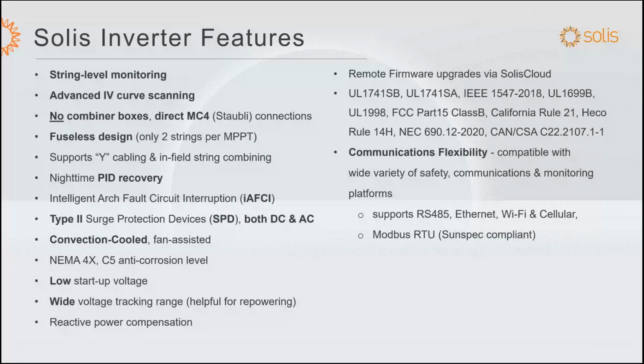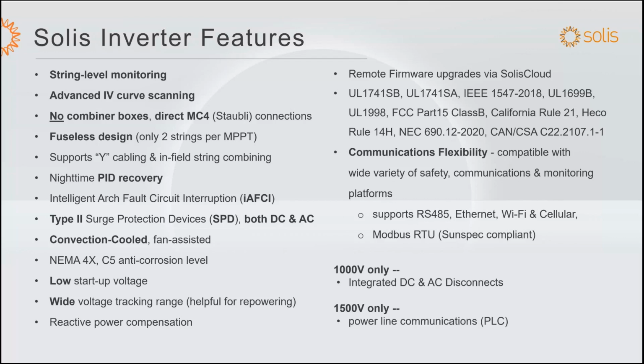And in terms of communication flexibility, we have our own communication data loggers, or we could work with any third-party platform. The important thing is we're Modbus RTU or SunSpec compliant, so whatever you have, we could communicate with. Some of the features of the 1,000-volt only inverters are integrated DC and AC disconnects, and on the 1,500-volt inverters, we have PLC capability, if that's the preferred method for communications, and we're also in the process of working on DC coupled storage for release in 2025.